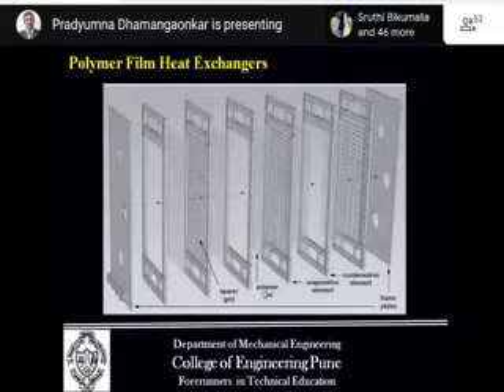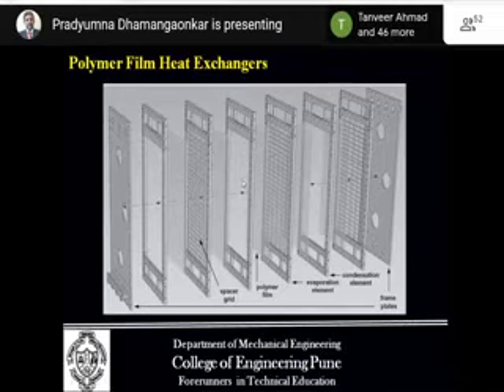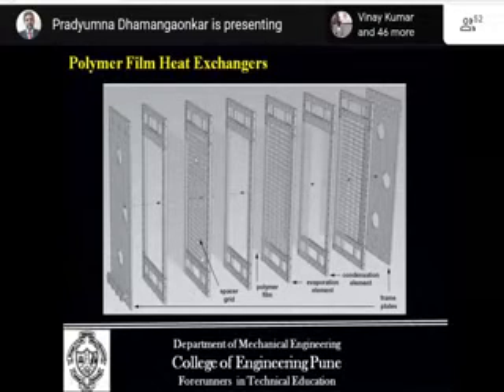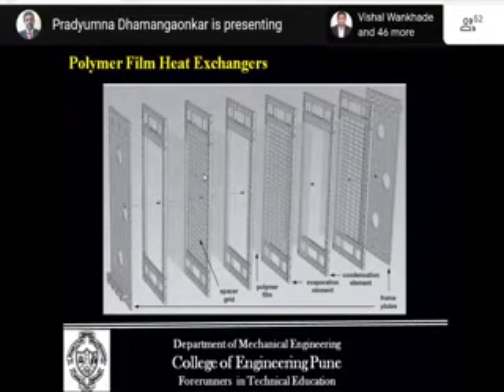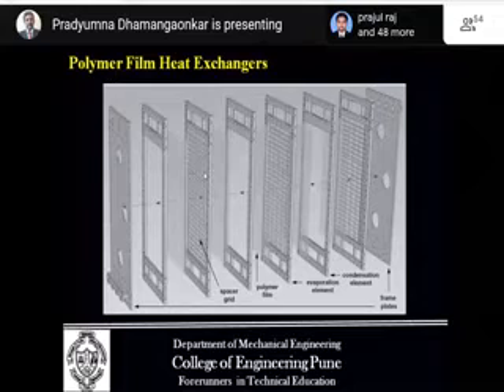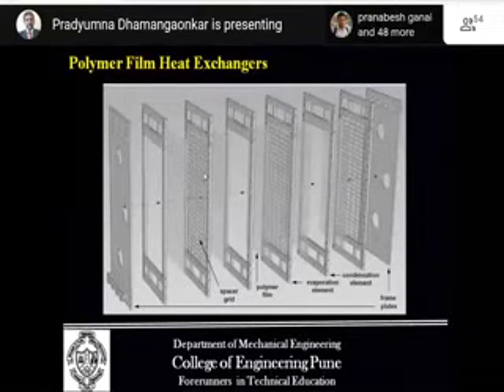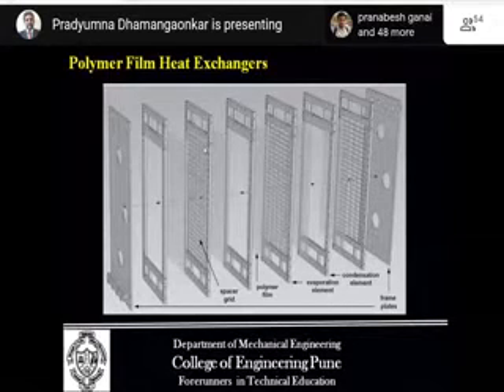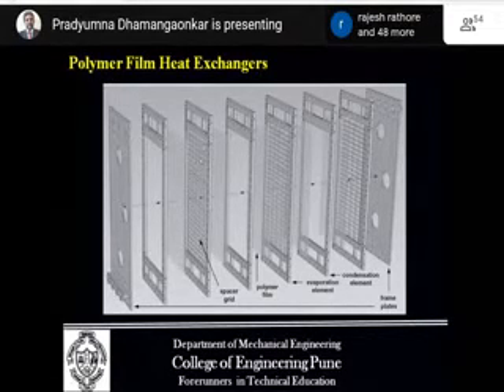With this, the researchers have tried to go for a polymer film heat exchanger. As shown in the figure, the metallic plates are replaced by polymers. And in between the two polymer films, a spacer grid is provided. This spacer grid helps in creating turbulence. As you know, in the conventional plate type heat exchanger, the form on the plate, that is the array, offers easy movement and distribution of the fluid and creates turbulence. The similar type of operation is achieved with the help of the spacer grids.